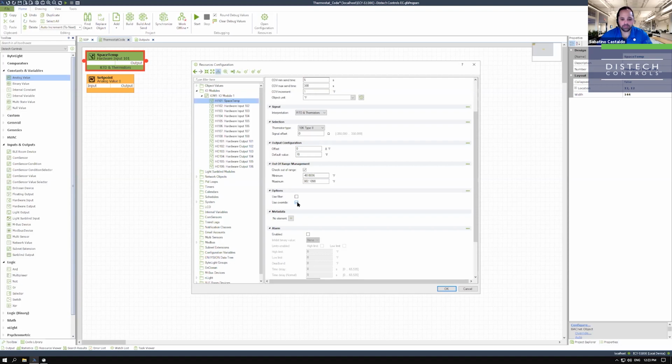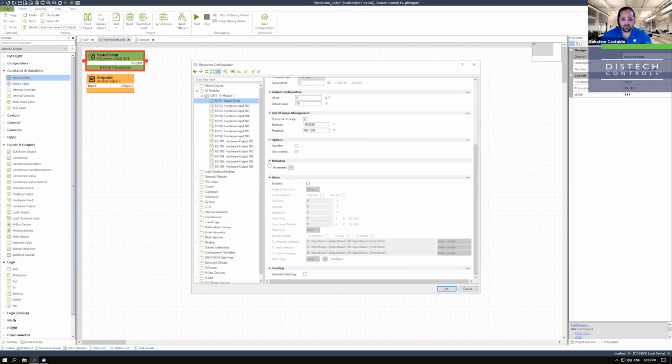Use override. This is something that allows us to take advantage of an EC sensor or sensor that has those day-night mode setback buttons or override buttons. Basically, they shunt the resistance. By checking that, we pick that signal up and we'll pulse it to our override output. And by doing that, we could use that as a free input for anything else we want to do in code. Metadata, we'll talk about that later. That's really something for Envision, Express Envision.